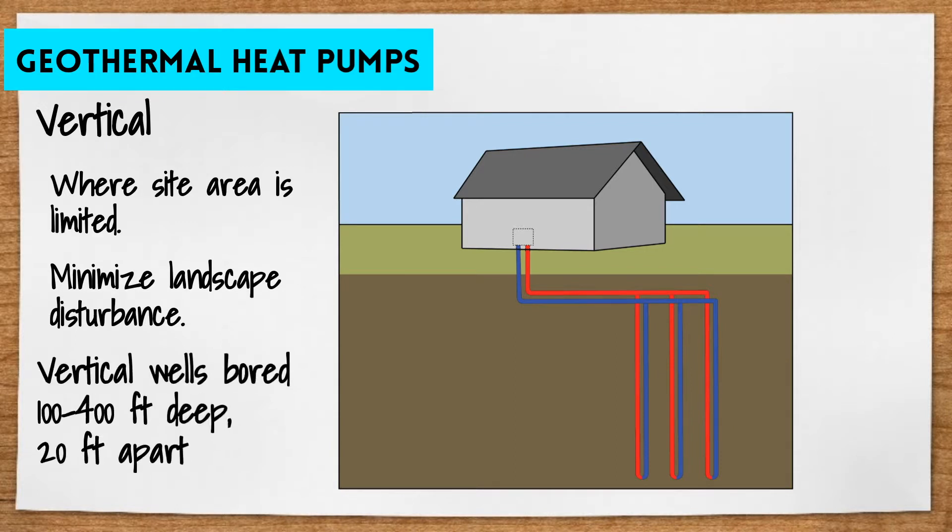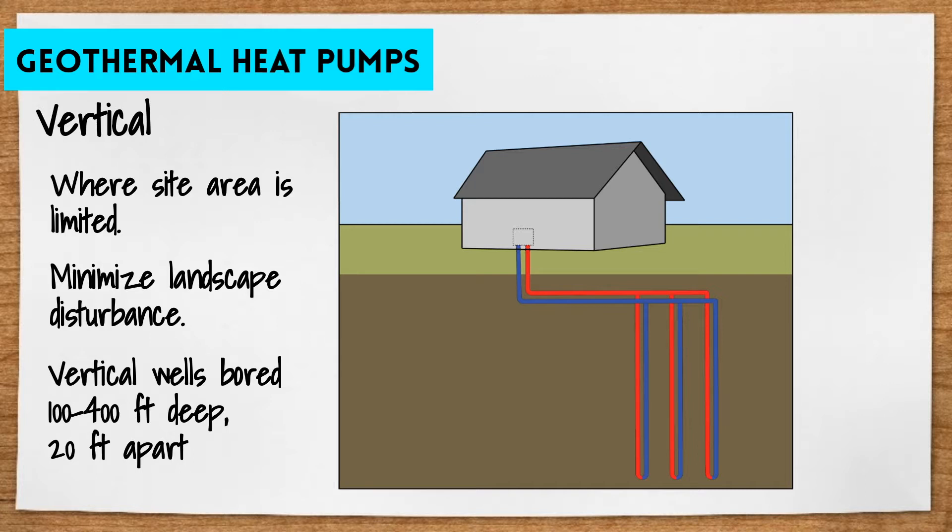In this system, vertical holes are bored about 20 feet apart from one another, going 100 to 400 feet deep. Each hole contains vertical loops that are connected with horizontal pipe placed in trenches and connected to the heat pump in the building.